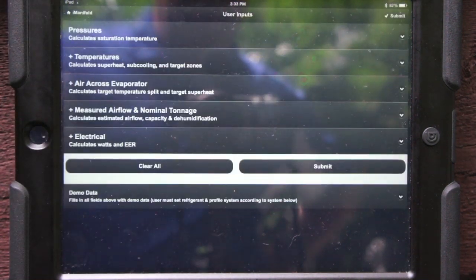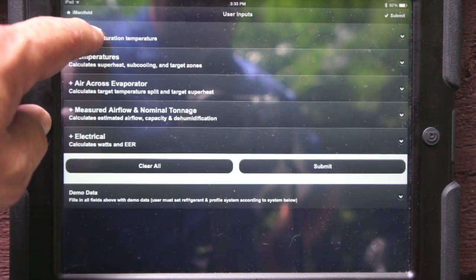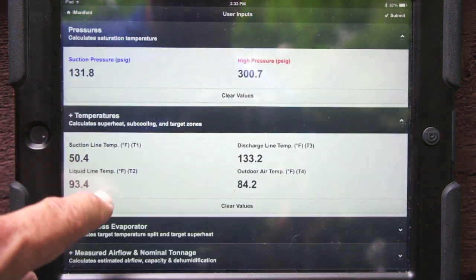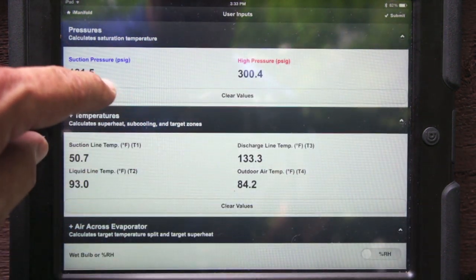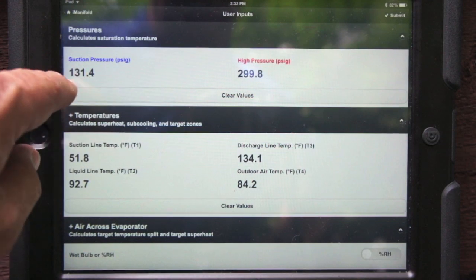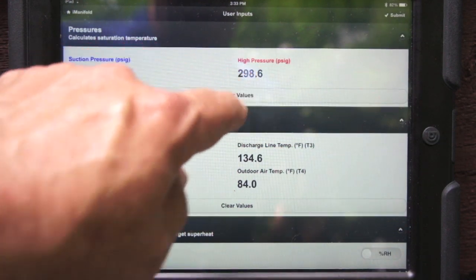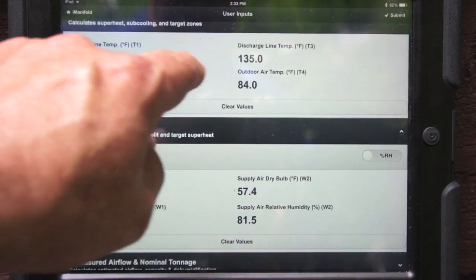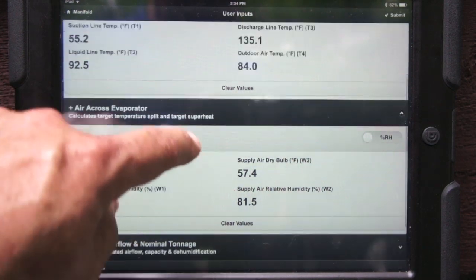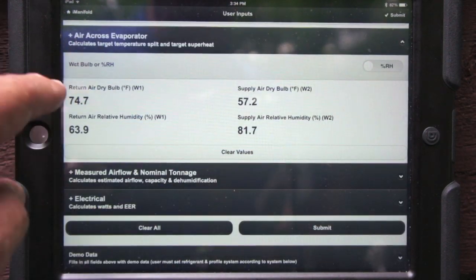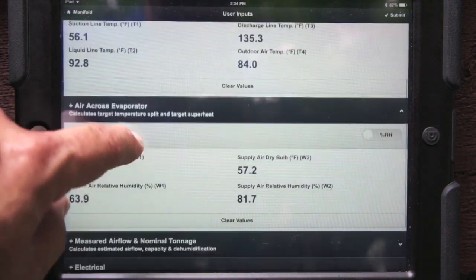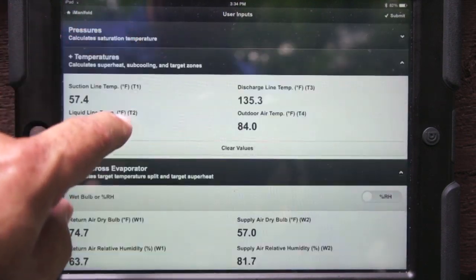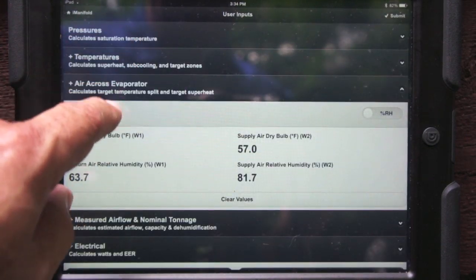Some huge changes in the user inputs now. If you look now, I'm going to open a bunch of these up here. Anything that's coming in real time, suction pressure, the high pressure, the suction line temperatures, discharge, outdoor air, none of those are editable fields, because all that information is streaming in real time. So we can leave these shut. There's nothing that we need to adjust there.